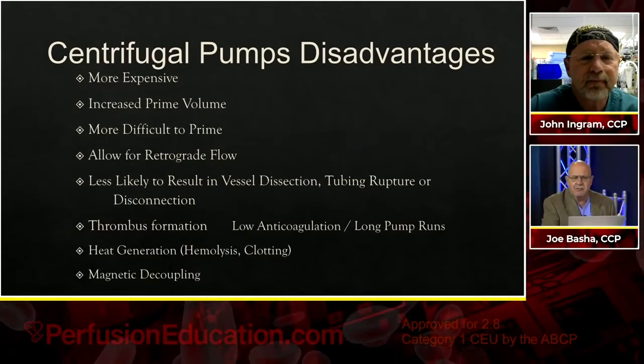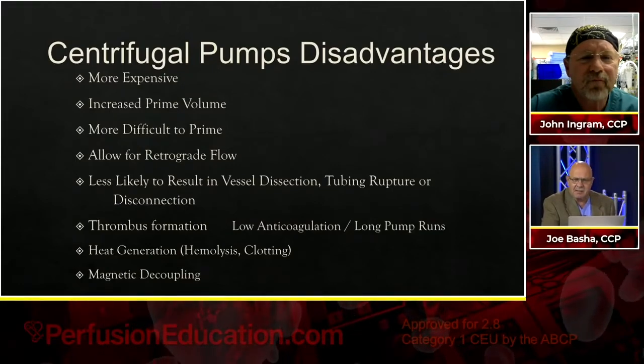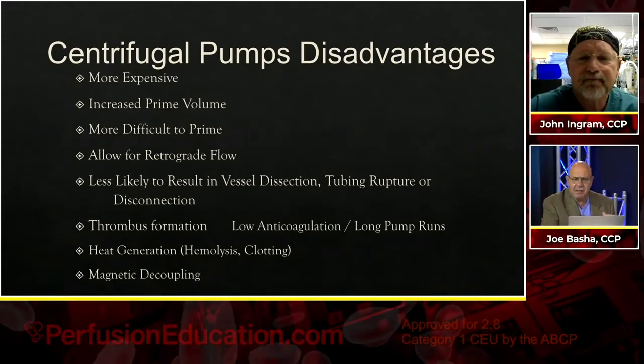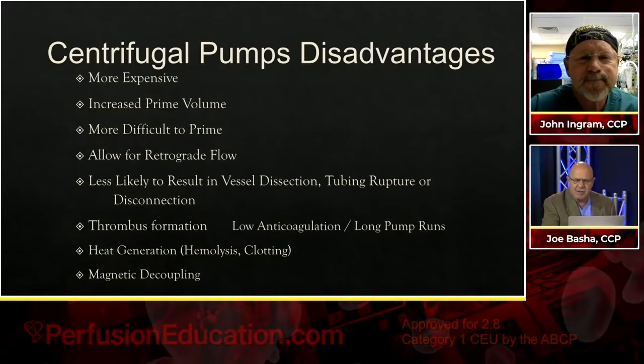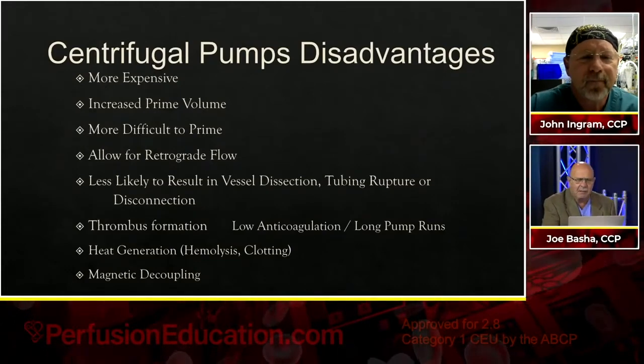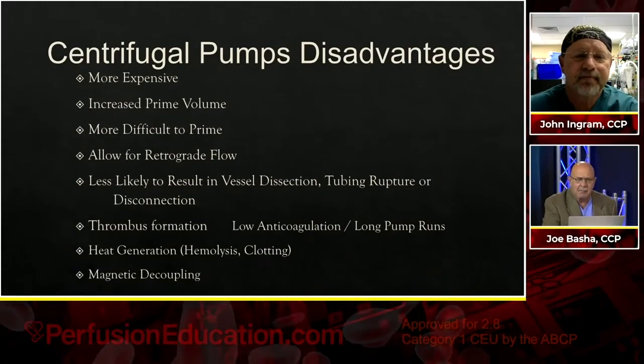Okay. So on the retrograde flow, there's been debate about having a one-way valve in the main arterial line to avoid that problem. It's the typical duckbill valve, which would work very effectively. But people are very hesitant to do that because if you did get air into your centrifugal cone, it's very easy to take it out, rotate it so that the outlet is facing straight up to your oxygenator, and then in a controlled fashion, open that line and let it reprime and then put it back in and go back on pump and not have any problems with it.